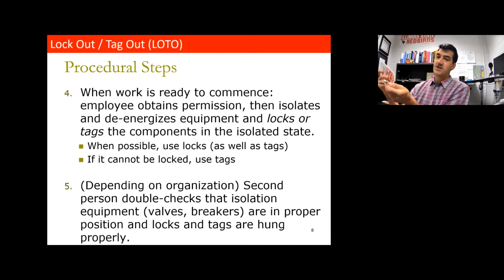So if you were going to de-energize the circuit breaker, you'd put the lock through it, then take the tag and write who is doing the work and what work is being done, attach it there, and lock it. Then you take the key with you, and the circuit breaker is locked in the de-energized state. If someone asks why it's locked out, the tag tells them exactly what's going on and who to contact with questions.